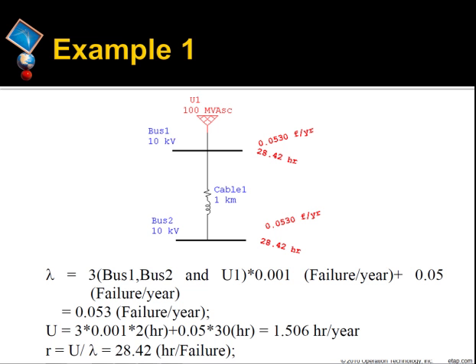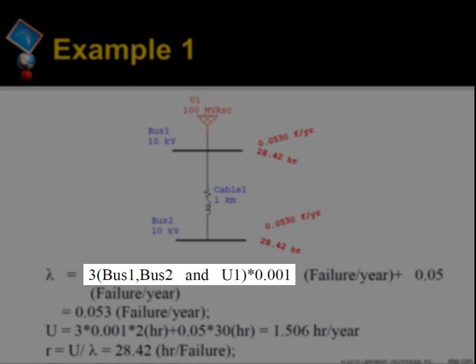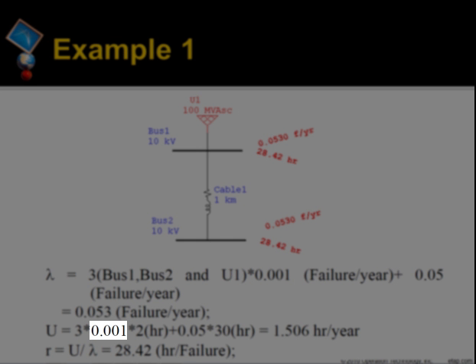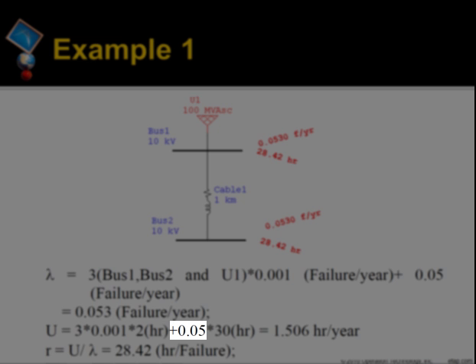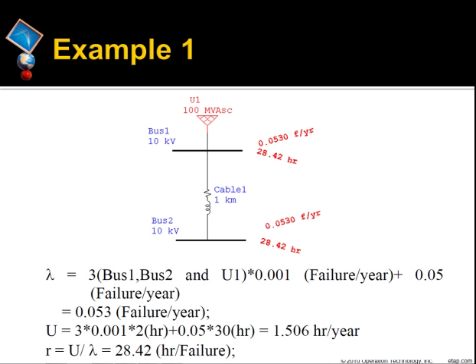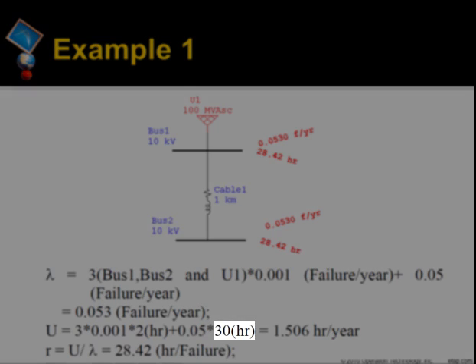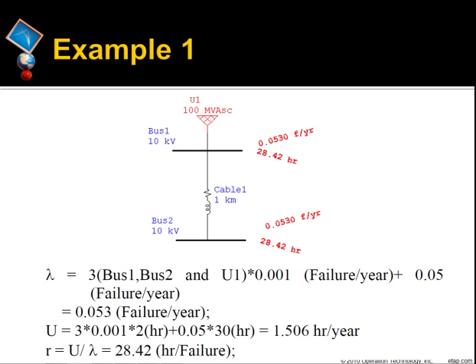Now let's look at a simple radial system example — Example 1. The failure rate for the utility, bus 1, and bus 2 is equal to 0.001, and the MTTR is equal to 2 hours. The failure rate for the cable is equal to 0.05 failures per year per kilometer, and MTTR is 30 hours with length equal to 1 kilometer. You can do a quick hand calculation as shown. As you can see from ETAP calculations, bus 1 and bus 2 have the same reliability indices since there is no protective device to isolate a fault.